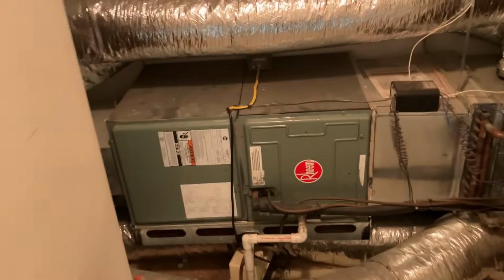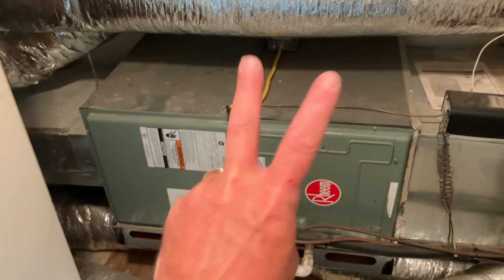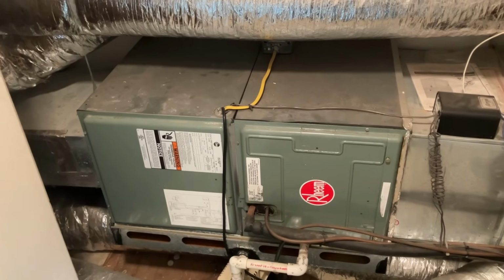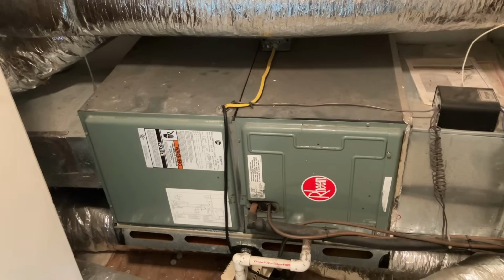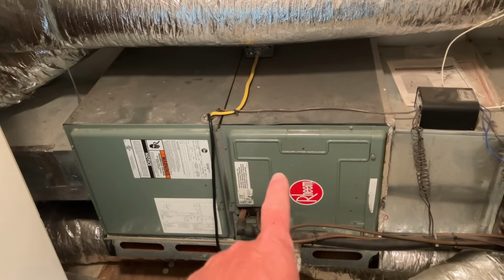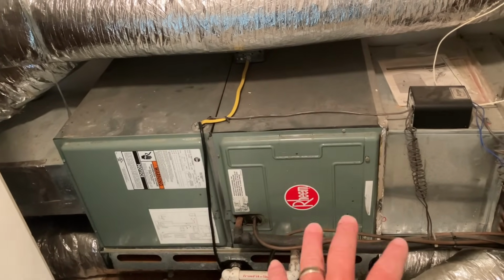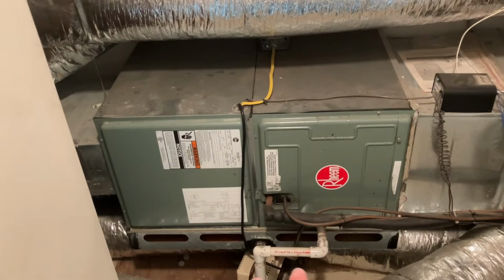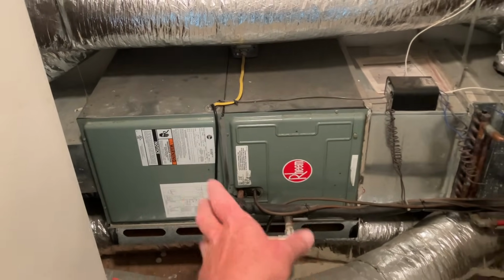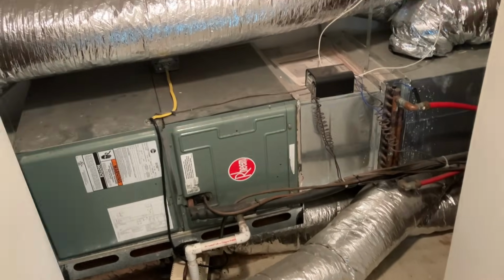All right, we are here for part 2 of the 2 ACiQ 3-ton heat pump HVAC system install. We're taking out 2 Rheem air handlers. We already took out the outdoor condensing units, and we're going to replace some line set and put in 2 new air handlers. It's going to be a night and day difference. It's dual fuel, because we have the hydro coil off the boiler and the heat pump capabilities of the system. We're going to revamp all of this. In that corner, deep in there, there's a little knee wall for the attic, and that's where our new line set is. We'll get it replaced, easy peasy.